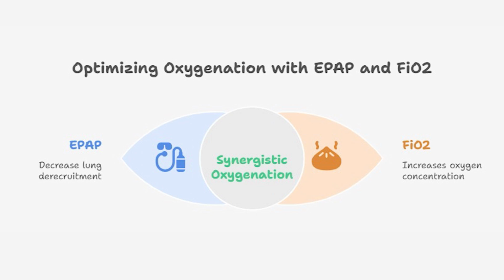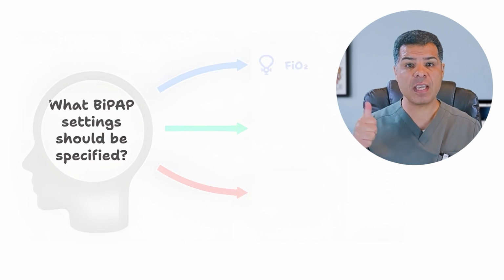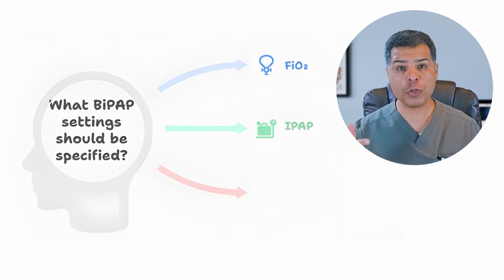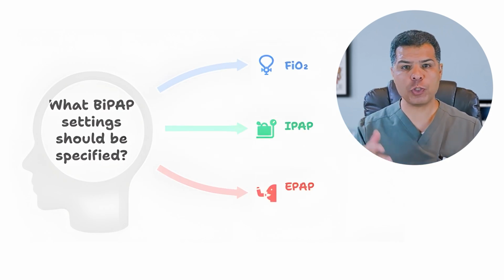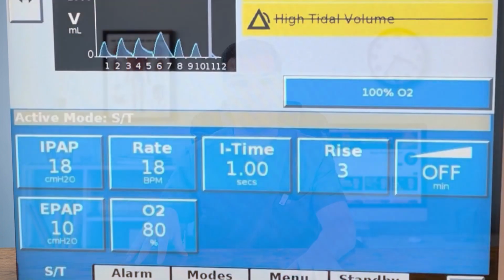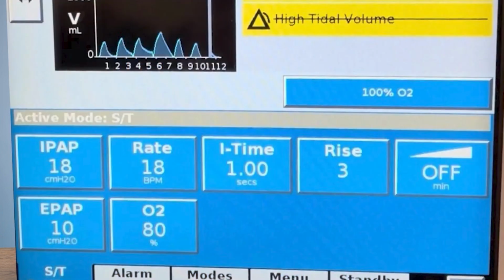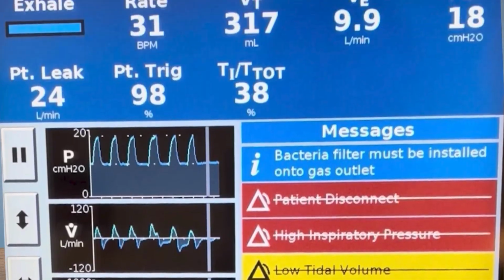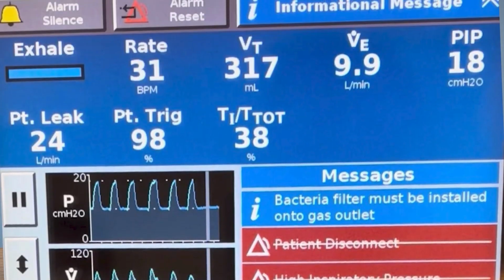Now, EPAP and FiO2 are the two values to play with to improve oxygenation when using BiPAP. When ordering BiPAP, you will need to specify 3 key settings: the FiO2, the inspiratory pressure, the IPAP, and the expiratory pressure, the EPAP. Take a look at this BiPAP screen. The IPAP is set to 18 centimeters H2O here. The EPAP is set to 10 centimeters H2O, and FiO2 is set at 80%. The peak inspiratory pressure reads 18 centimeters H2O.